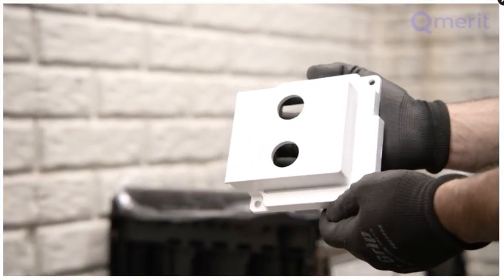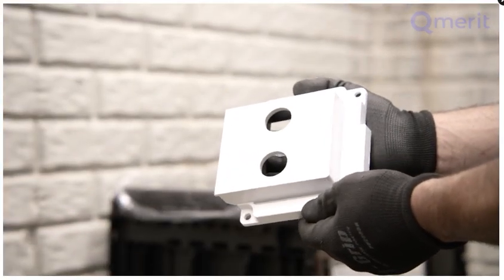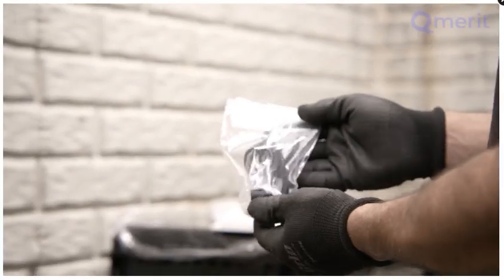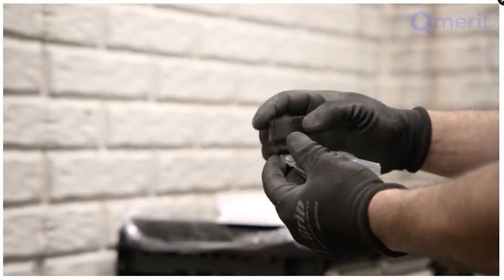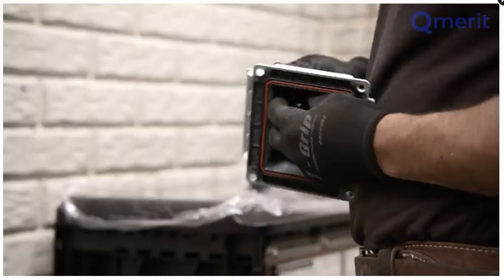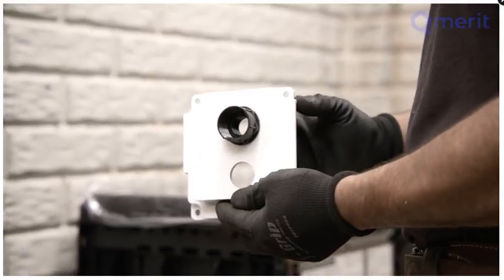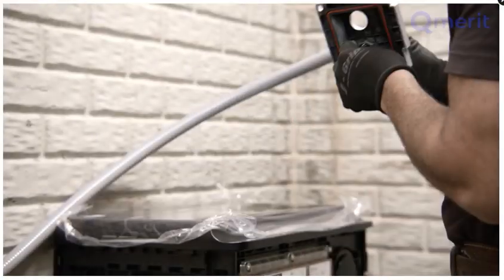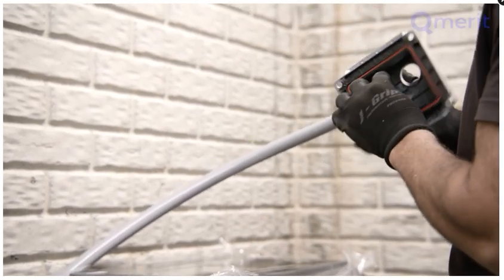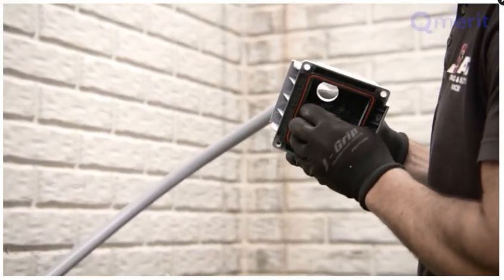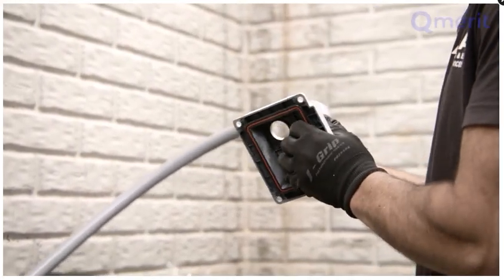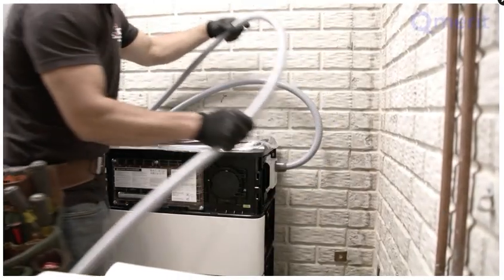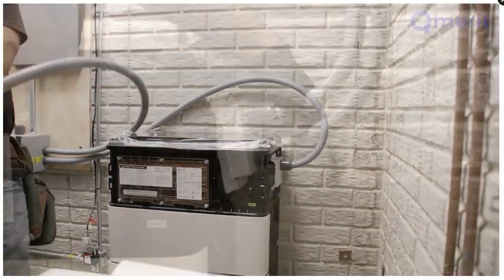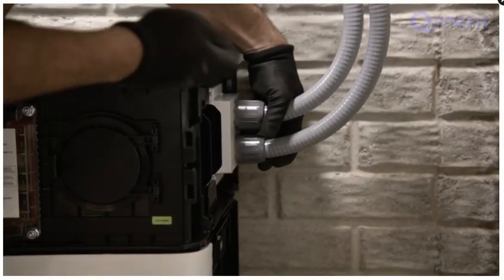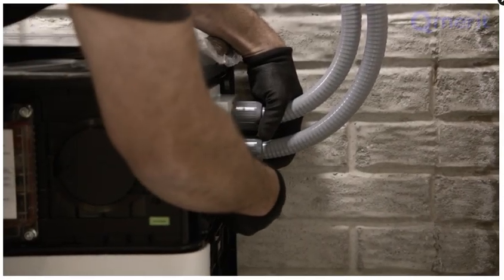Find the side sealing cover. There is 1 3/4 communication cable gland and 1 3/4 power cable gland. If you're using a 1-inch conduit, these are reducers for the side sealing cover. We're using 3/4 inch conduit in this example and will not need to use these reducer glands. Use flexible conduit when attaching the side seal cover to the BCU. There are 4 studs in the BCU to receive this plate.